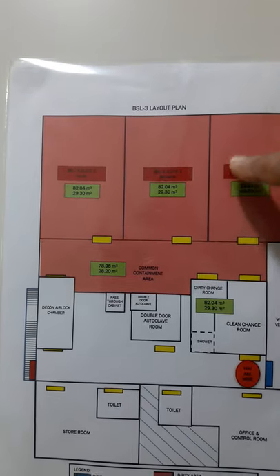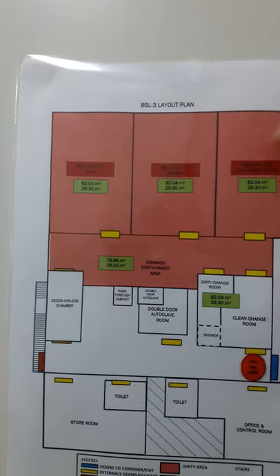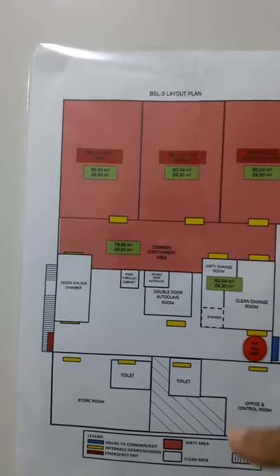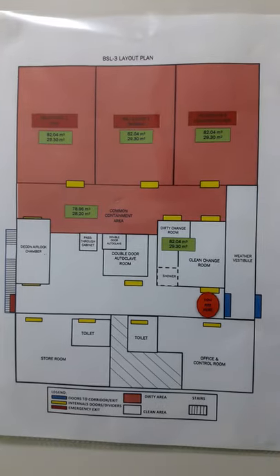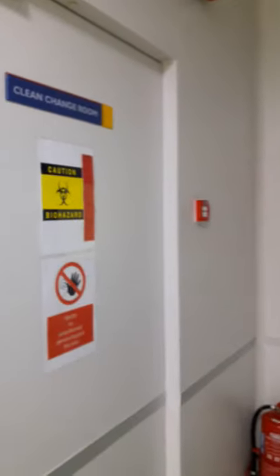All the work involving pathogens, such as diagnostics and experiments, takes place in these three suites. They are under negative pressure as compared to the zone at which I am standing right now. This is the way in which engineering control is applied at this facility to contain microbes to their respective laboratories and working areas.